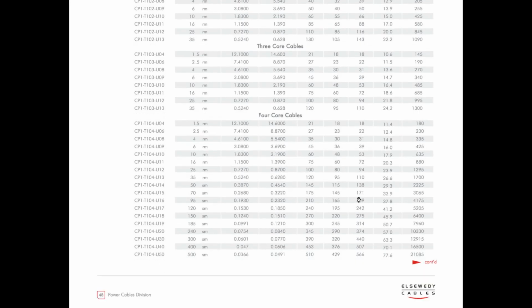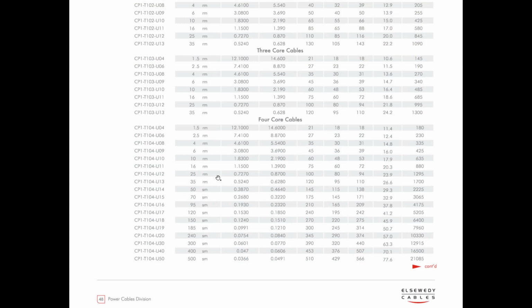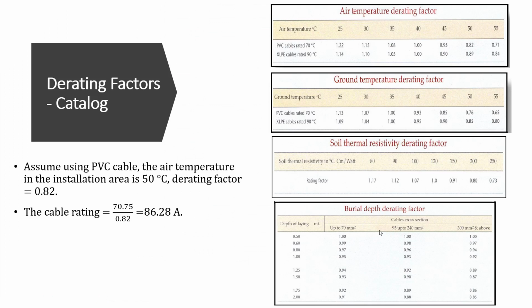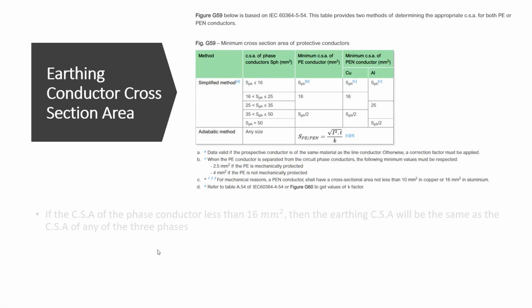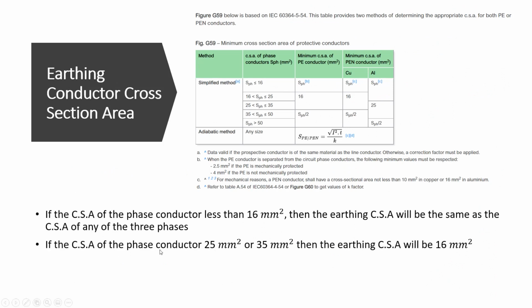Okay, so let's go back to our slides. We said that 25 square millimeters, with 94 ampere, can satisfy the requirement. So we have 4 multiplied by 25 square millimeters, which is the three phases and neutral, plus 16 square millimeters for the earthing. Now someone will ask me, how can we know the neutral and the earthing size? We discussed this in the previous lesson. We said that if the phase conductor is 25 square millimeters, such as in our case, the earthing cross-sectional area will be 16 square millimeters. That's why we said 4 multiplied by 25 plus 16 square millimeters for the earthing.